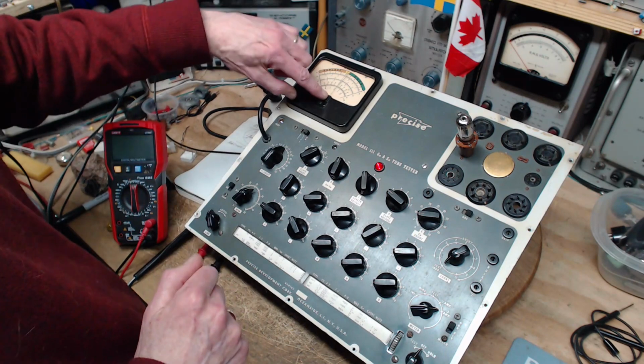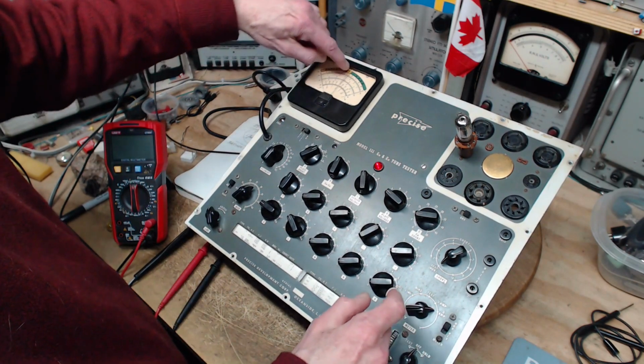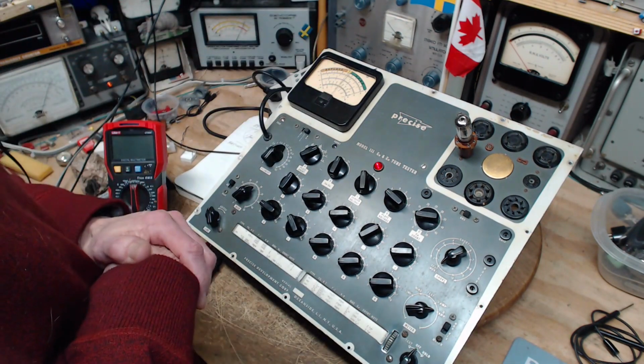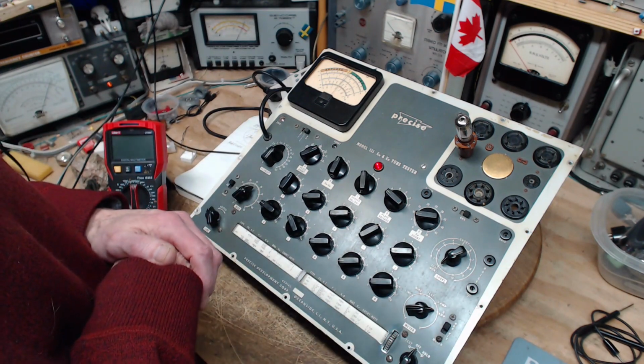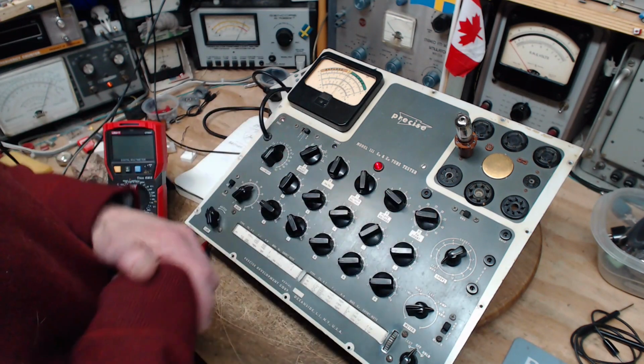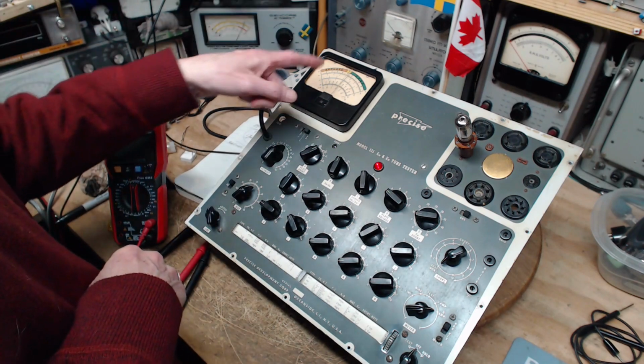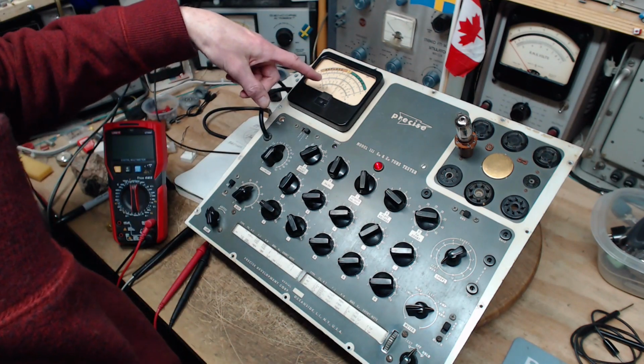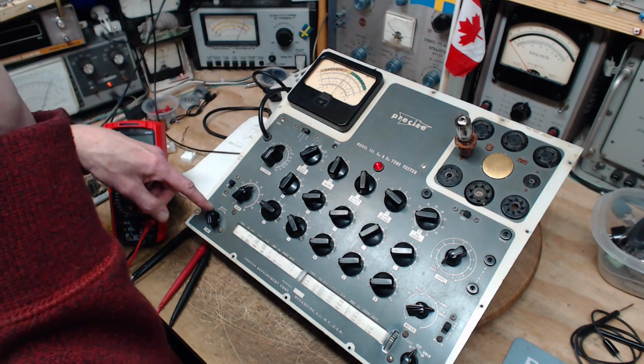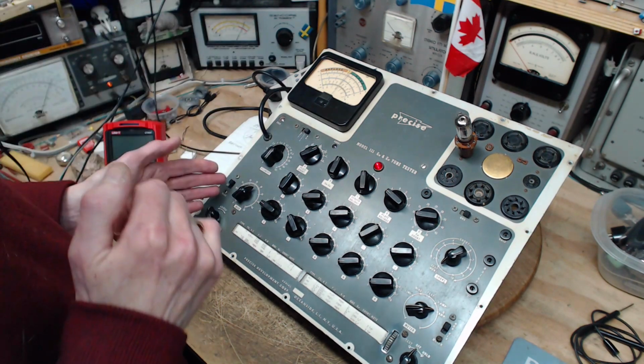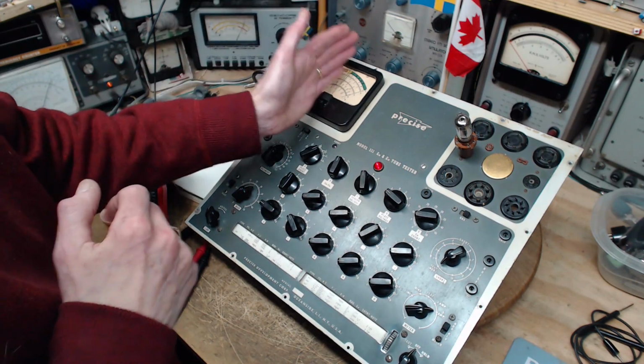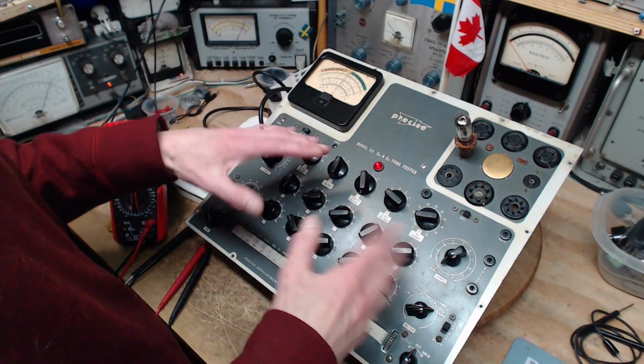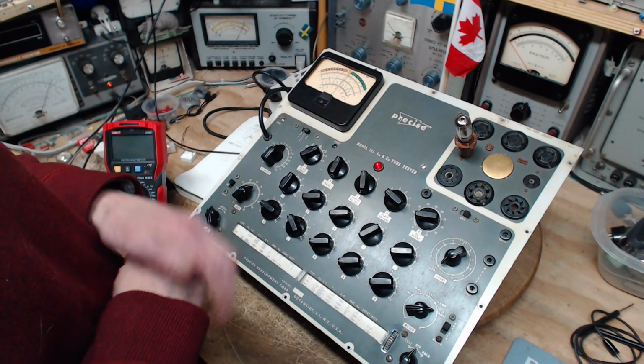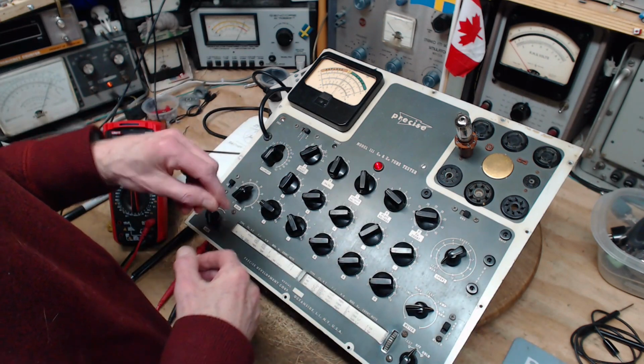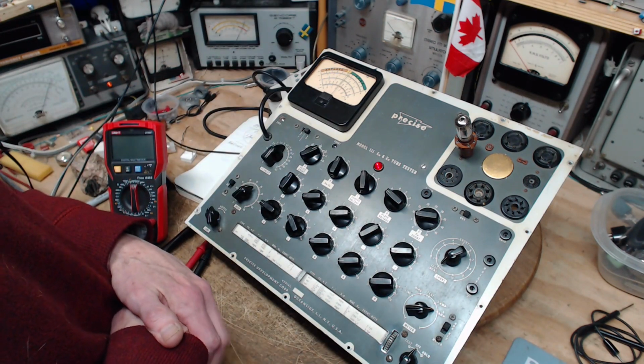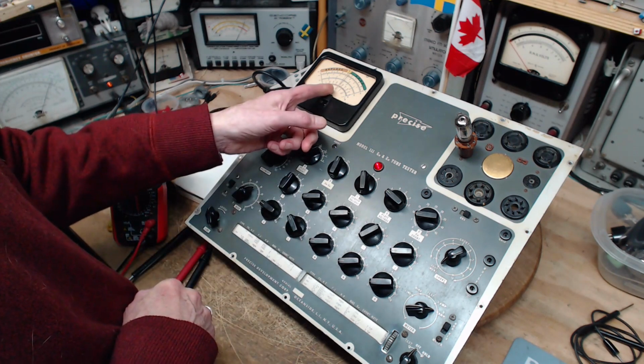Okay, so the tube current on the 3.3 amp scale should be up the middle. It's showing it a little high. That's probably just another calibration thing. Could be all the calibrations I've done have gone off a little bit since I adjusted the bias, or not the bias, the line adjustment, because that would have meant it was previously adjusted incorrectly. Every time I set this to center, I would have had the tester not quite in the state it should be in. So previous tests were one way, now I've got this corrected, so the test is going to be a little bit different. So this is probably just a calibration error.